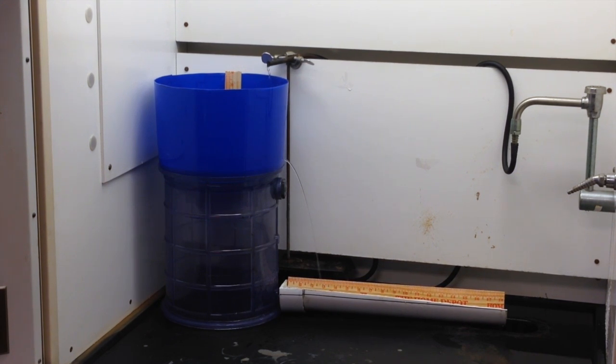and that makes for not only drier areas at the edge of those distribution patterns, but also a thinner film going down the fill. And on tall towers or high-load towers, or towers operating at peak demand, that results often in significant evaporation and thinning of the film towards the bottom of the fill pack, and scale formation within the tower fill, where at a full flow or full pan depth or full thickness of water film on the fill, scaling in the tower fill does not occur.